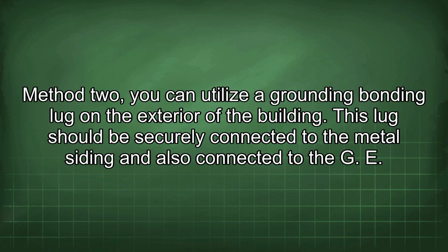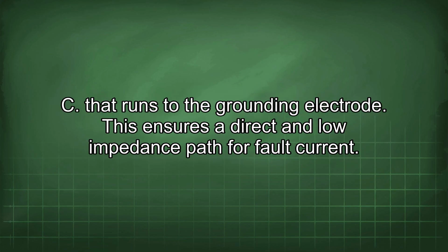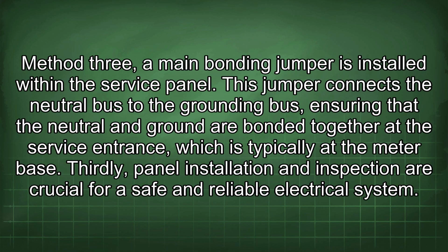Method 2, you can utilize a grounding bonding lug on the exterior of the building. This lug should be securely connected to the metal siding and also connected to the GEC that runs to the grounding electrode. This ensures a direct and low impedance path for fault current. Method 3, a main bonding jumper is installed within the service panel. This jumper connects the neutral bus to the grounding bus, ensuring that the neutral and ground are bonded together at the service entrance, which is typically at the meter base.